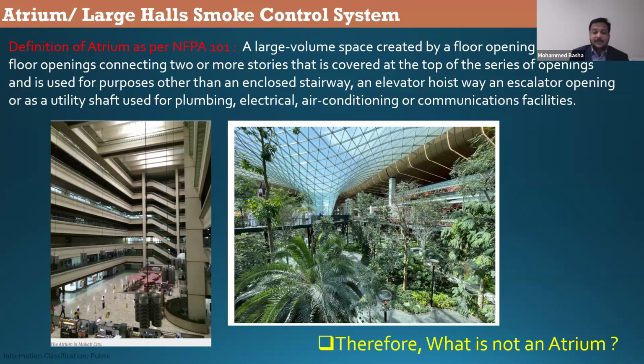Why is it? Because the atrium is a vertical open space, open to the communicating spaces next to each other. As you can see in the figure, left or right, the right side is more familiar to us because it's from HIA, Hamad International Airport. The left side is taken from the internet, just to show you an example. You have a big open area and multiple levels communicating to the atrium, which means open to the atrium. If any fire happens in the atrium, it will pass to the communicating spaces as well. So we should ensure that the smoke generated by the fire is taken up directly, without allowing the smoke to pass inside, to maintain tenable conditions for the occupants to go outside. This is the purpose of the atrium smoke management system.